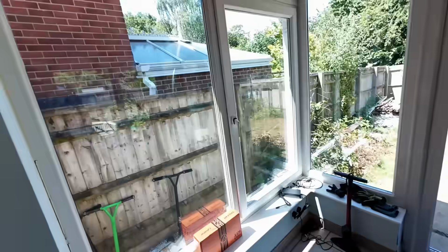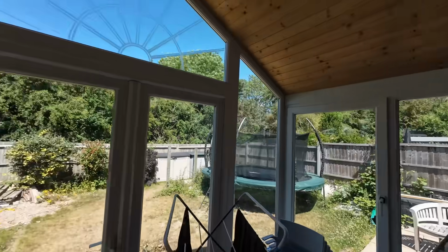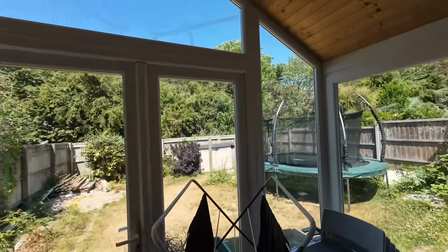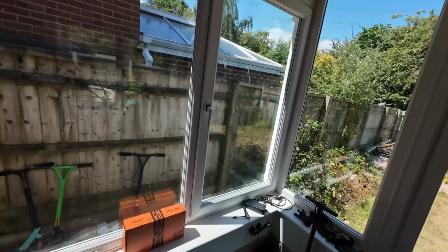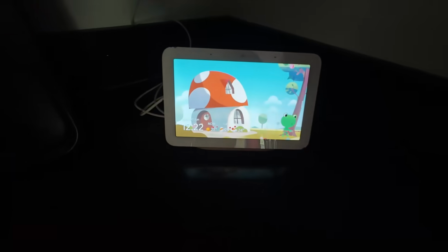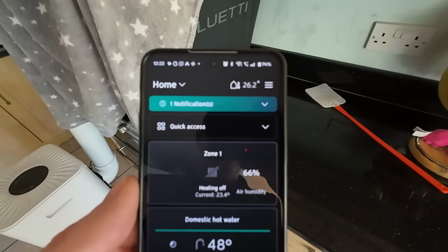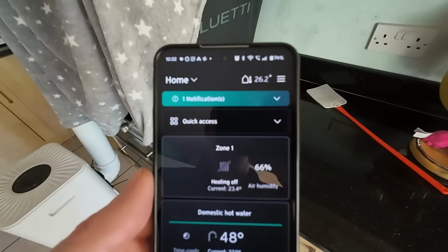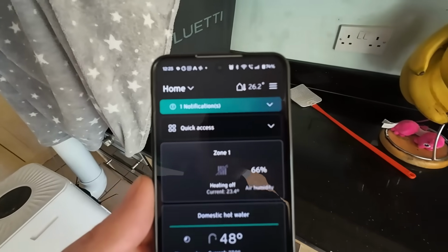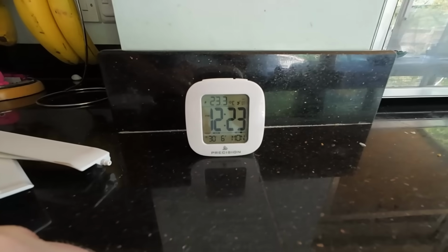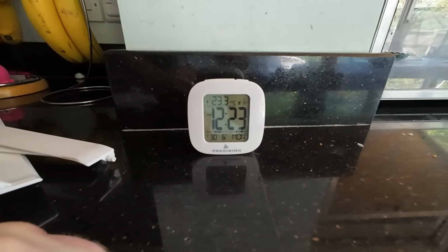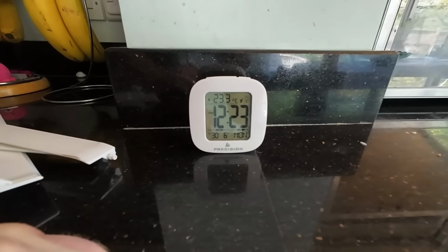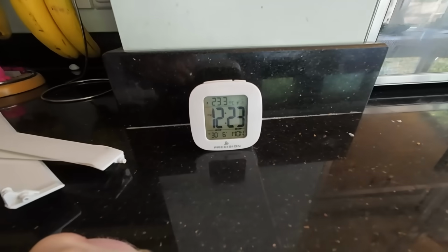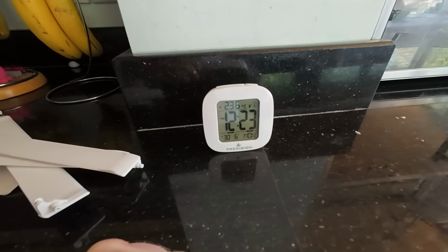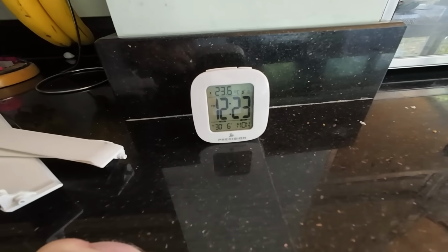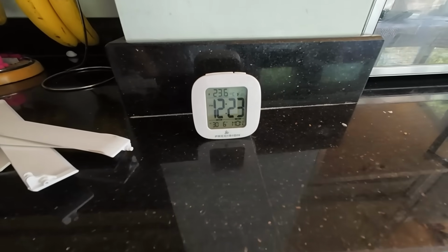Oh, we've got clothes hanging everywhere, brilliant. But as you can see, we're surrounded with lots of glazing. So on a hot day like today, let's have a look at the temperature. Google says 27 degrees. The Vaillant outdoor weather sensor says 26.2. The internal temperature is 23.3 and rising. It's 12:23, the sun is directly overhead and slowly starting to come in through the glazing, so this room is going to warm up quickly.